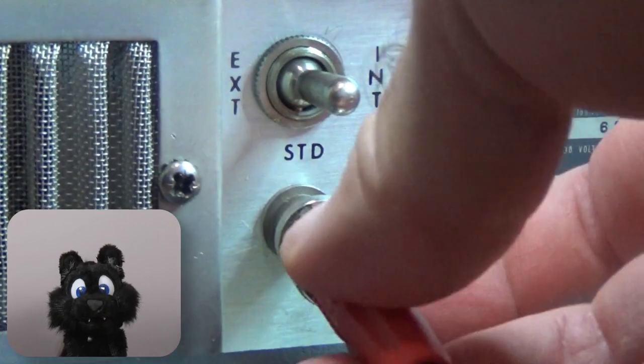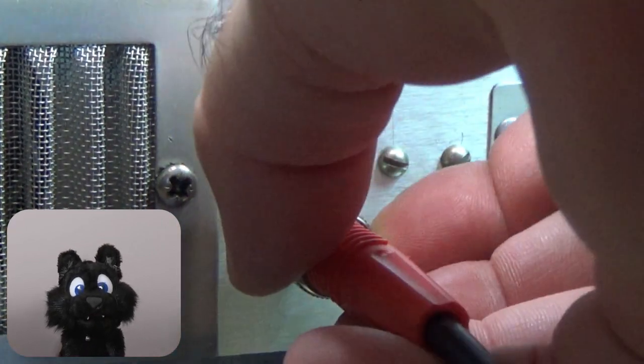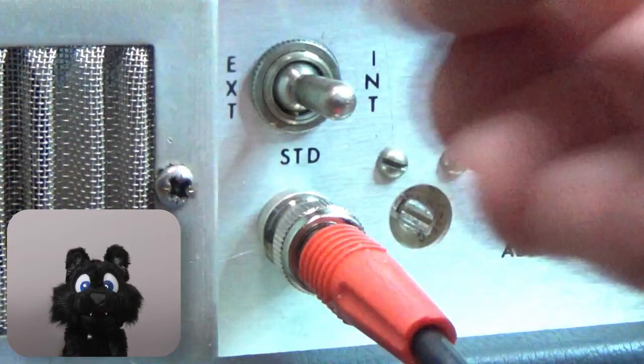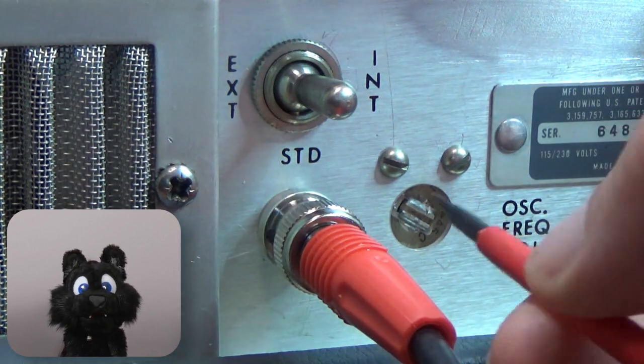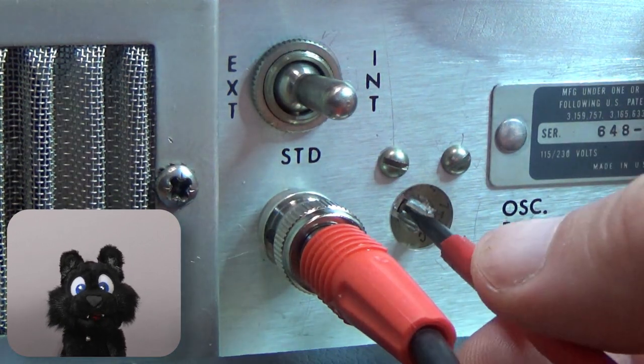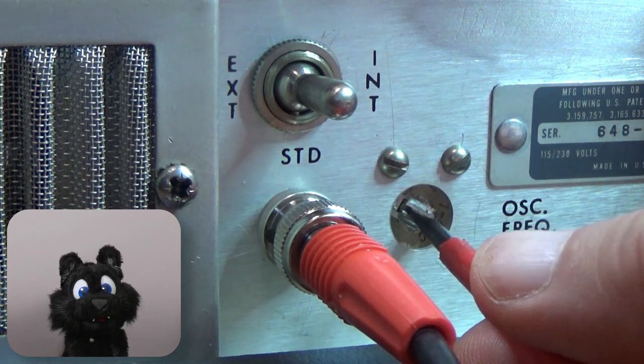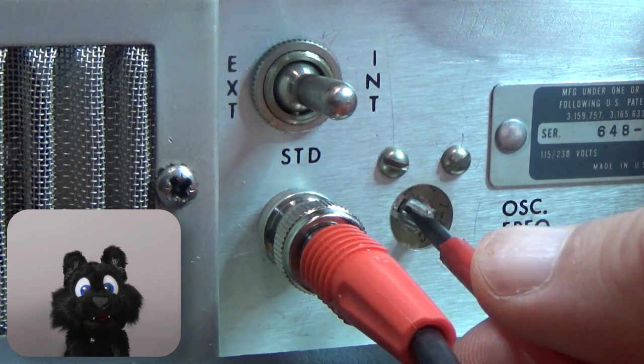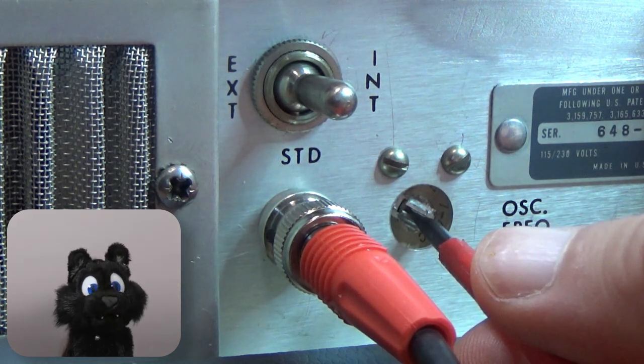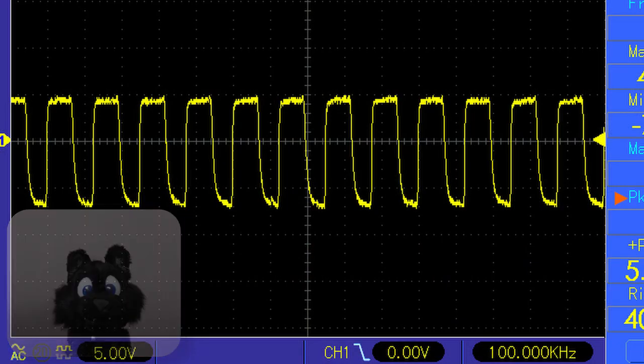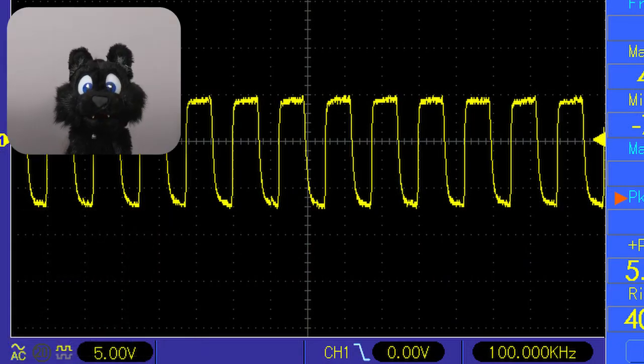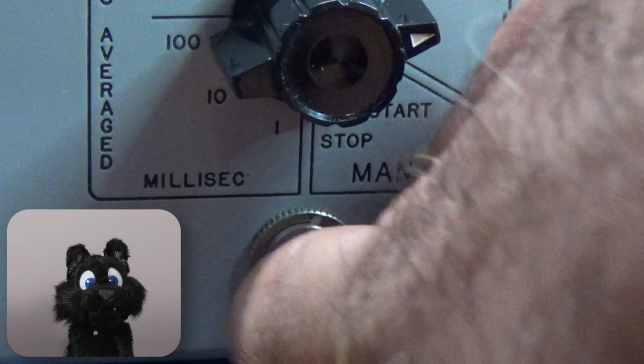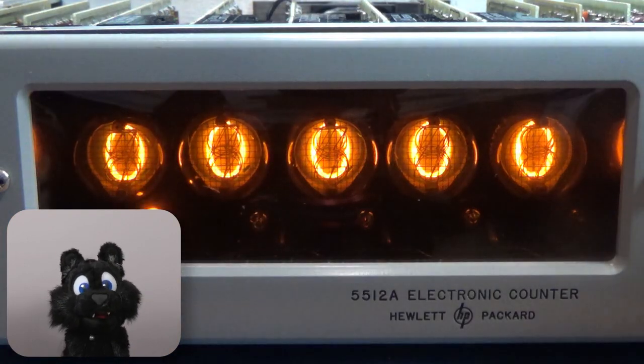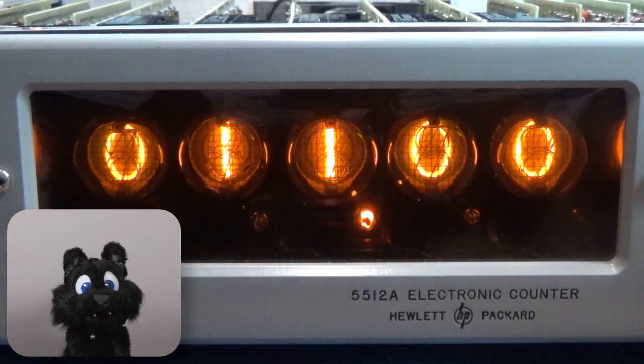The reference frequency is a 100 kHz quartz signal, but there's a trim cap near the rear to tune that. It can even be tuned without opening the case. The external clock input turns into an internal clock output when the internal clock is selected. So I use my digital scope to get it as close to 100 kHz as possible.